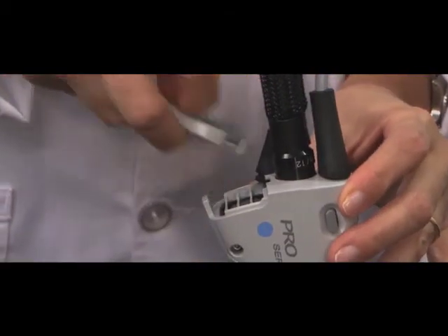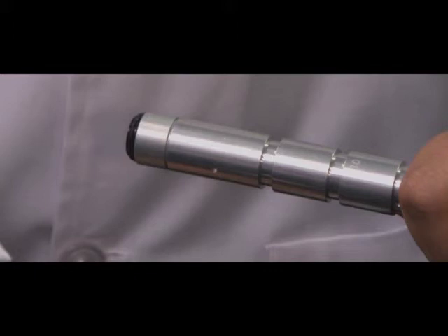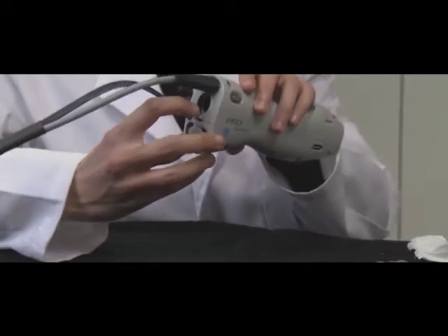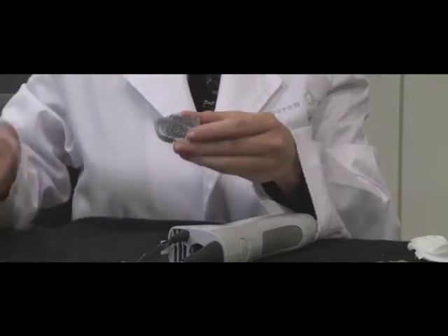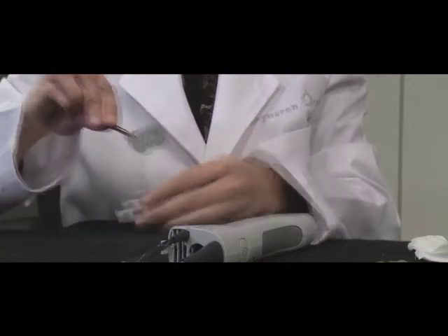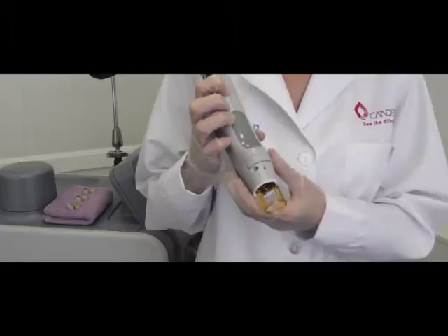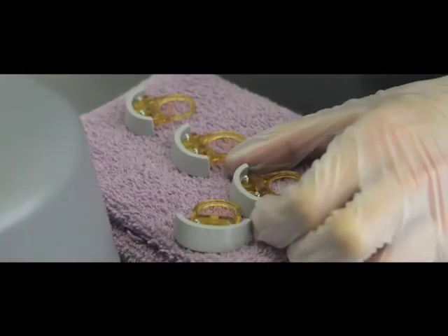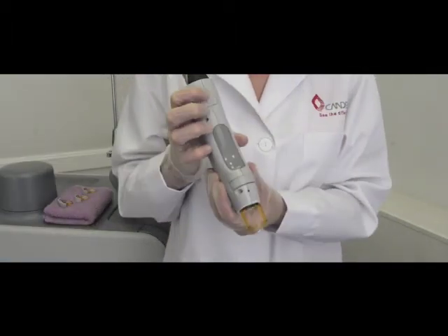The handpiece components are the filter, button release for slider attachment, inner tube for slider, and window holder. The filter is removed and cleaned once per week. You may wish to do this twice per week with heavy use. The window holder is easy to remove and replace. During longer hair removal treatments, placing multiple window holders at the ready is useful for rapid changing. At the end of the treatment, all windows can be removed and cleaned at the same time.